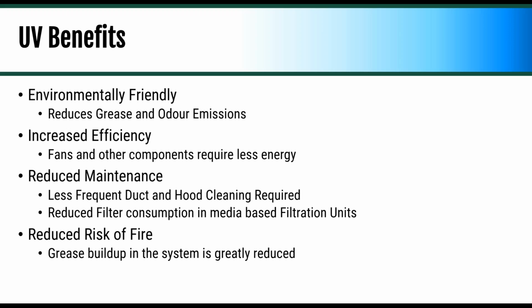It increases efficiency because filter boxes and fans are getting less grease on them. They're operating at more optimal conditions. Part of that is reduced maintenance, so less frequent duct and hood cleaning is required, and reduced filter consumption in media-based filtration units. We're working with Jimco right now to do a guaranteed reduction in filter consumption. I don't know what the exact number is going to be, but we're probably going to be using roughly 1/5 of the media, as long as we've got the properly sized UV system. Reduced risk of fire. We don't see it in North America, but in Europe, they've actually been able to work with underwriters to reduce insurance rates based on the reduced risk of fire.